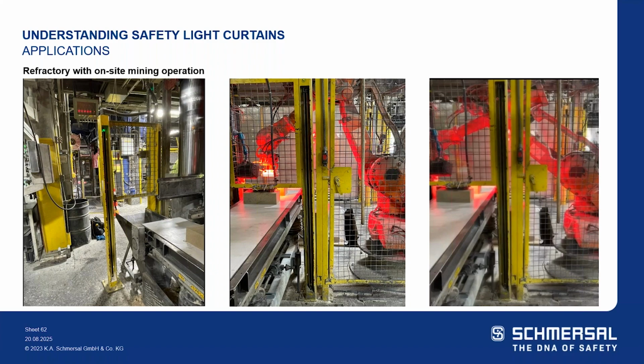They noticed that they had a good amount of flex and torsion in the Allen Bradley and the Omron light curtains when they started working with anything that was over 5 feet tall, as well as multiple failures due to damage from the weak housing design. So that was a key selling point for us as well, that our unibody construction, even though it's a lighter weight light curtain, it's a more robust, mechanically strong light curtain.